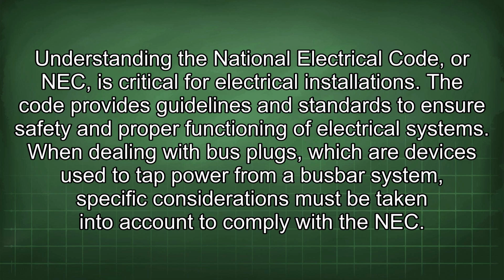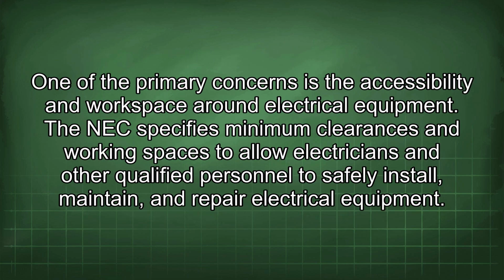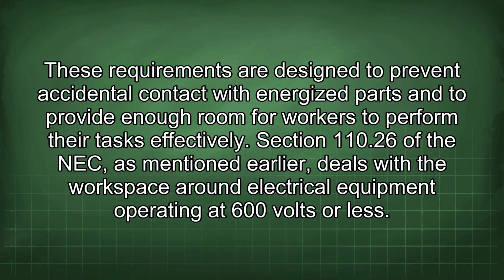Understanding the National Electrical Code, or NEC, is critical for electrical installations. The code provides guidelines and standards to ensure safety and proper functioning of electrical systems. When dealing with bus plugs, which are devices used to tap power from a busbar system, specific considerations must be taken into account to comply with the NEC. One of the primary concerns is the accessibility and workspace around electrical equipment. The NEC specifies minimum clearances and working spaces to allow electricians and other qualified personnel to safely install, maintain, and repair electrical equipment. These requirements are designed to prevent accidental contact with energized parts and to provide enough room for workers to perform their tasks effectively.